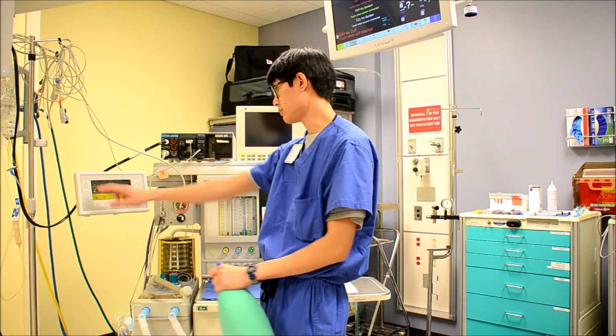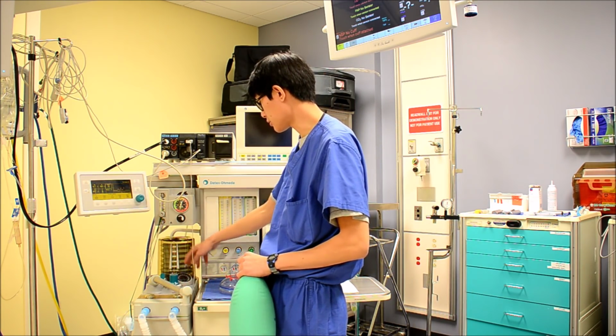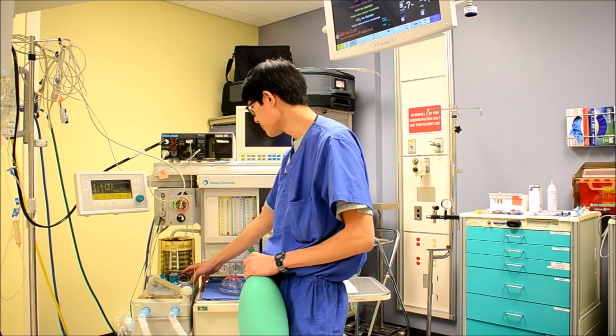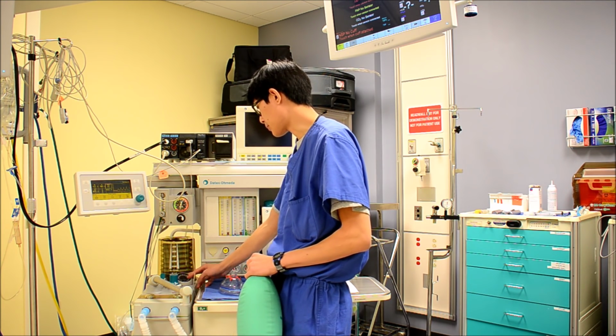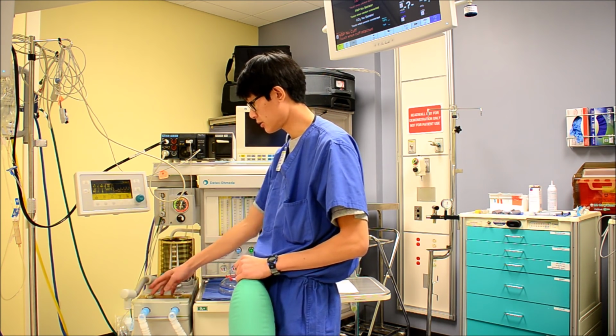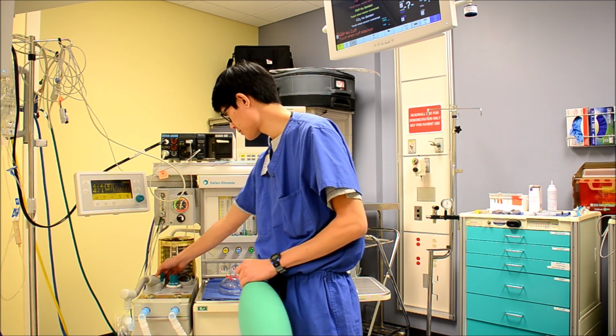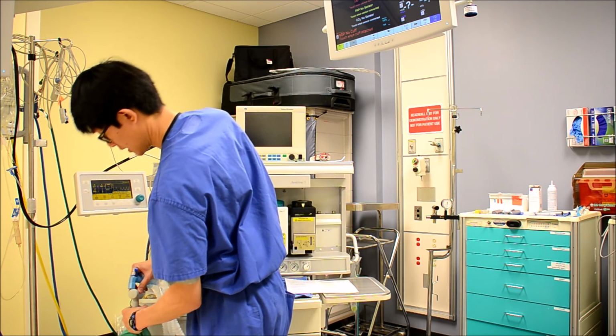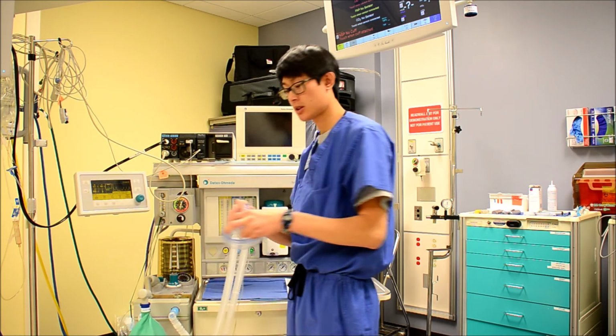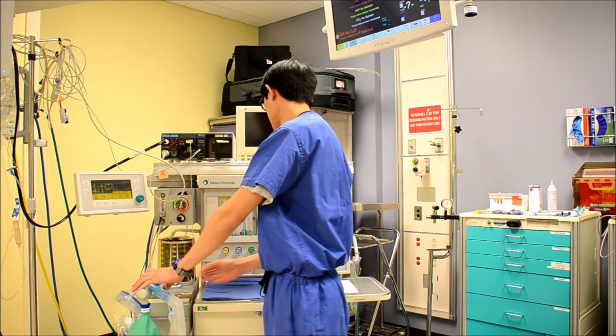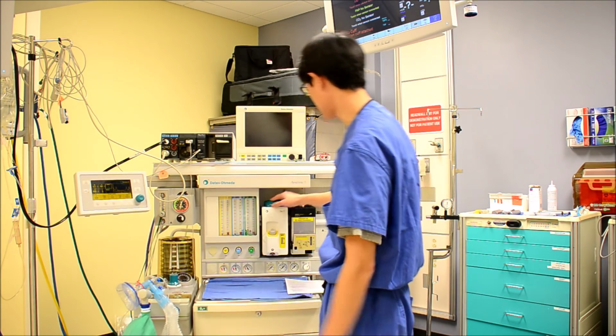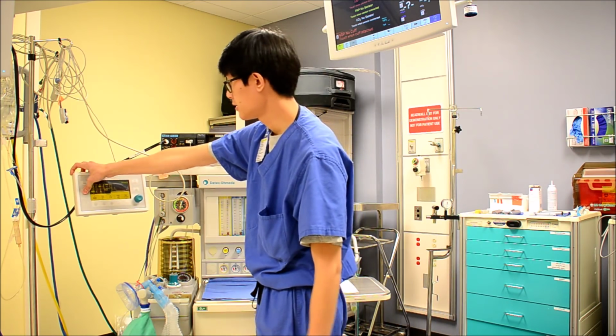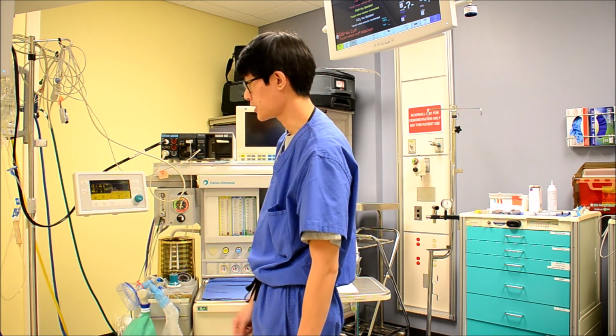That looks fine. So I'm getting the volume that I want, the bellows are dropping to the right volume. My pressure is reaching down to 0, and my valves are working properly. Put that back, get the face mask back on. Everything's off again. Just make sure you have your vaporizers off. Get your ventilator to standby, and you're ready for your next case.